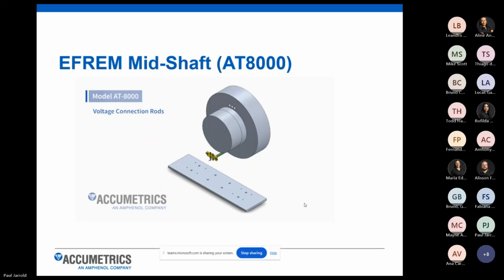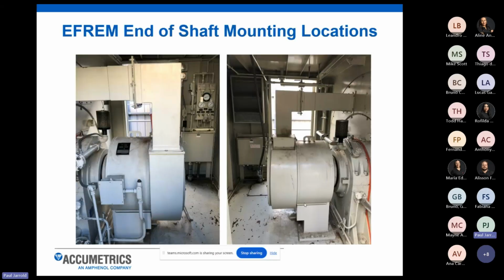Okay. Next, we're going to talk about our other system in the EFREM family. This is electrically the same. It functions the same way as the EFREM midshaft system. The only difference is it's a different mechanical package that's designed to mount directly on the end of a brushless exciter shaft, where we do have direct access to the end. So there's no permanent magnet generator. All your armature windings and diode wheel assembly for your brushless exciter are housed in one single compartment.